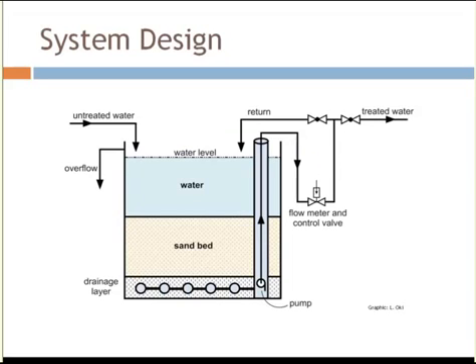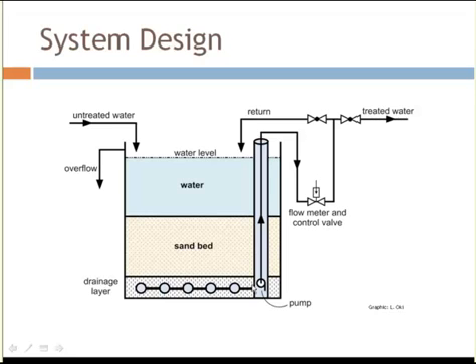Here is a graphic of how a slow sand filter might look. Untreated water is introduced into the sand bed container, with about a one-meter water depth. The sand bed is below that at a one-meter depth. Below that is an underdrain system consisting of a pipe manifold with perforated pipe and pea gravel to collect the treated water. That treated water is pumped out of the containment unit and through either a flow measuring or flow control device, and then out into the system for that water to be used.